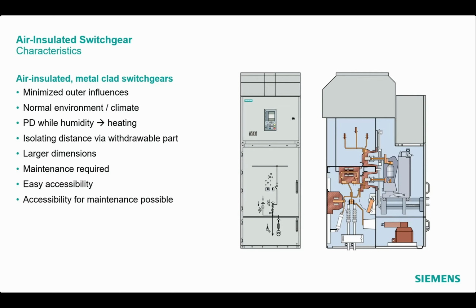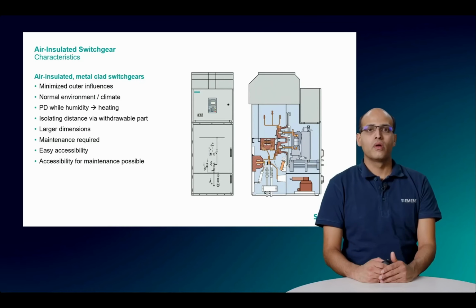However, AIS has a lower environmental impact as it uses air as insulating medium. Because of the inherent dielectric characteristics of air, the AIS have comparatively larger dimensions in order to ensure proper isolating distances. The withdrawable part in the AIS helps to provide isolating distance, ensuring personal safety. The switchgears are easily accessible, especially for maintenance. However, because of the previously said reasons, AIS require regular maintenance to prevent the moisture and dust affecting the performance.